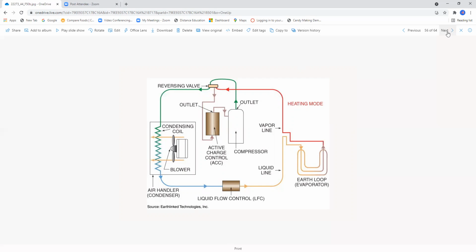Okay, notice that you have a four-way reversing valve up here. And notice we are in the heating mode. We have the earth loop, which is the evaporator. We have the liquid flow control, LFC. We have the air handler, the blower, the condenser coil, the active charge control that maintains the proper amount of refrigerant inside the system, the compressor, the outlet, which goes to the four-way valve. Remember, this is in the heating mode at this point.